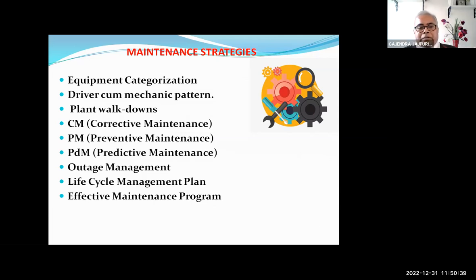Now, in the beginning, some of the audience told about history, so that point is also there. Now I will tell what things are covered in predictive maintenance: the diagnostic and performance data. Diagnostic means various techniques are available, sometimes online, sometimes offline, like vibration measurement, which we are repeatedly talking about, and the shock pulse meter, SPM, which gives an indication of cage failure or some bearing failure.